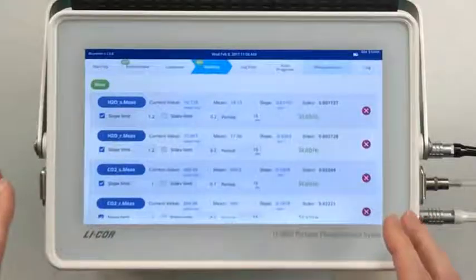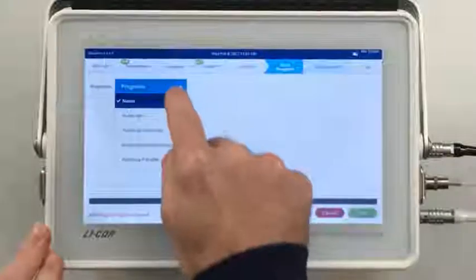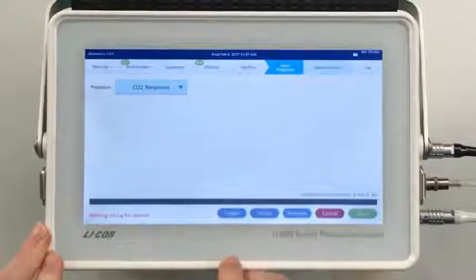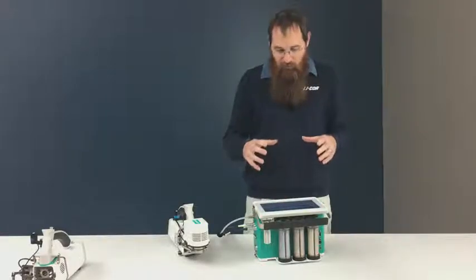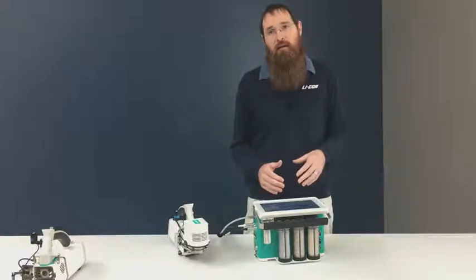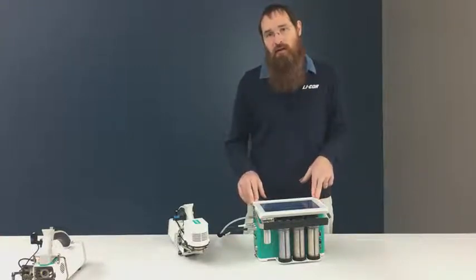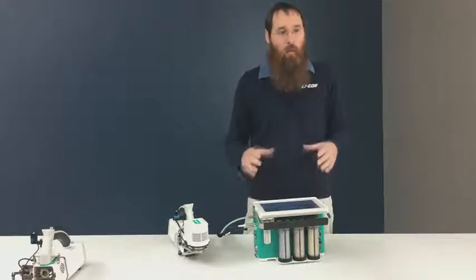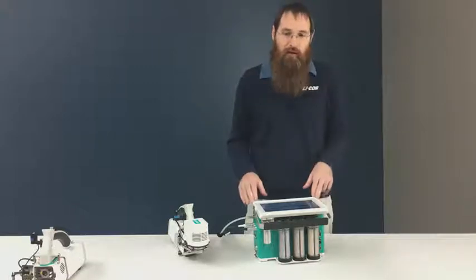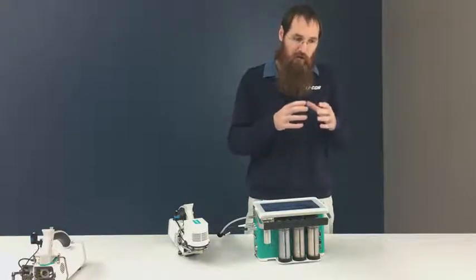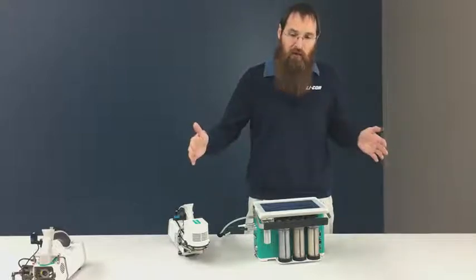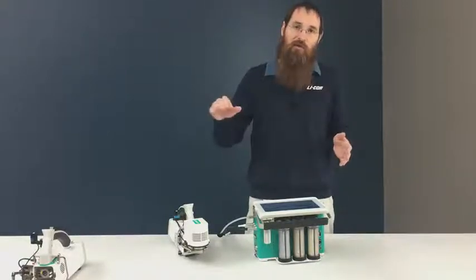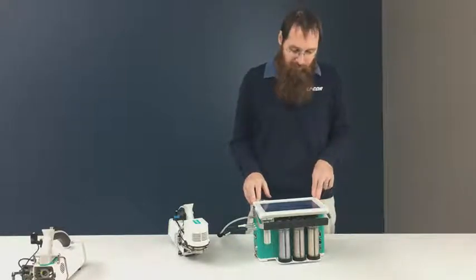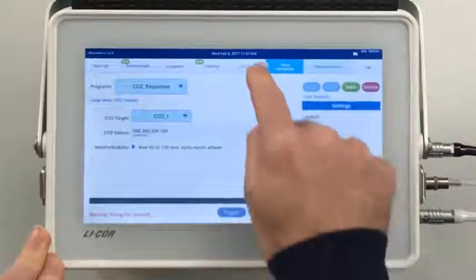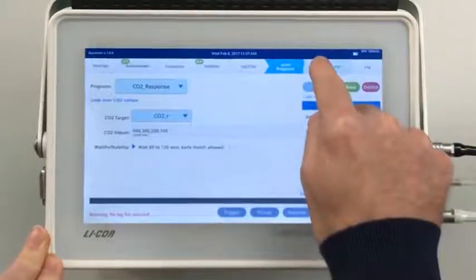But probably the most common use for them is related to these things called auto programs. And auto programs let me do things like CO2 response curves. If I tell the instrument a minimum and a maximum wait time, and I give it a stability definition, the instrument will use that stability definition to decide when the data is stable and log data for you. You can think about it as not just defining a time period in which you want it to record the data, but providing it with a window of time, and then the instrument can decide in that window whether things have reached stability and whether or not you have good data and it's worth recording. So that's what stability definitions are. I'll come back to log files in a second.